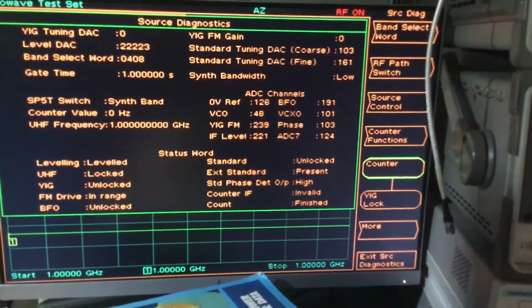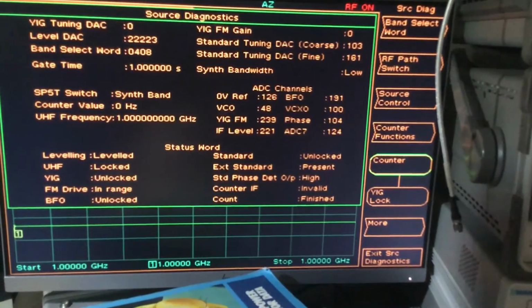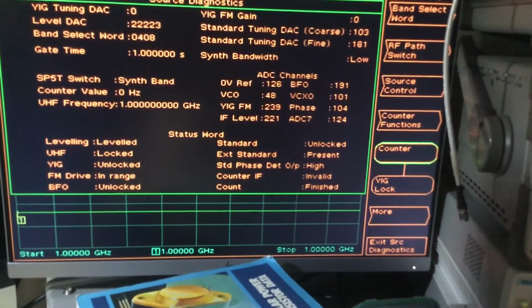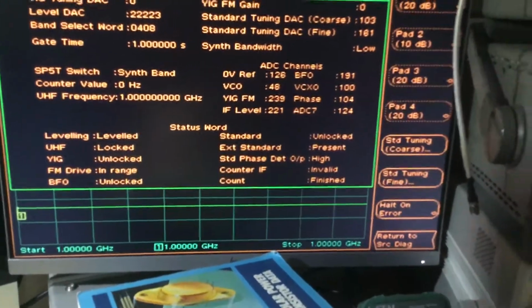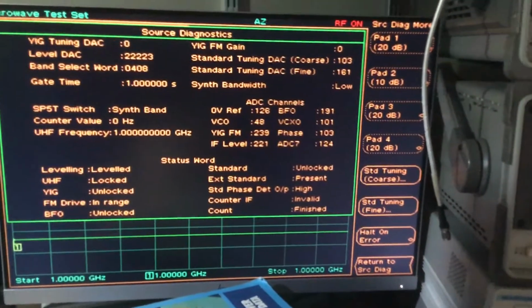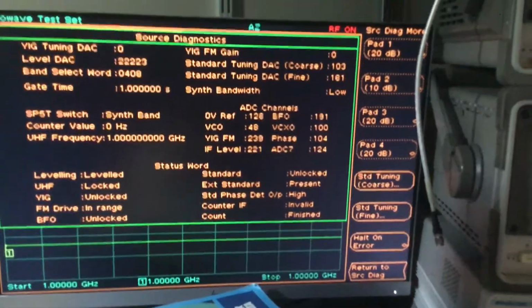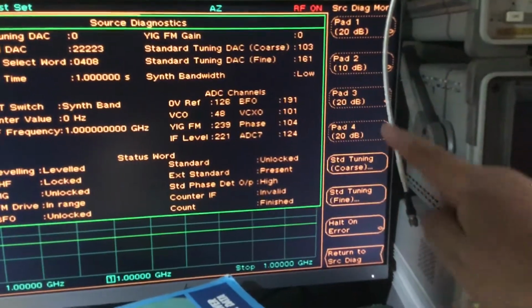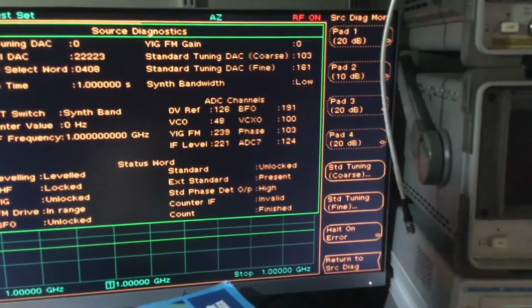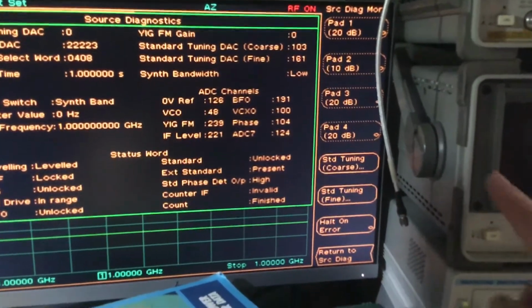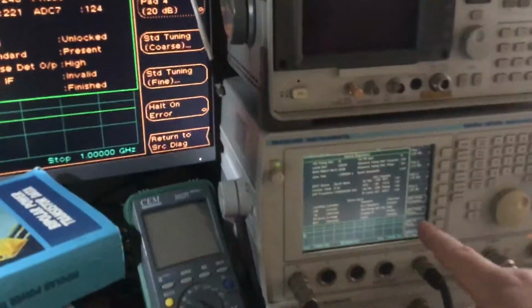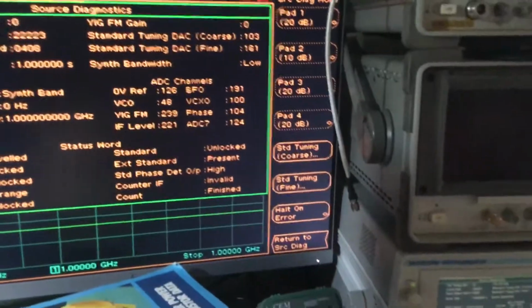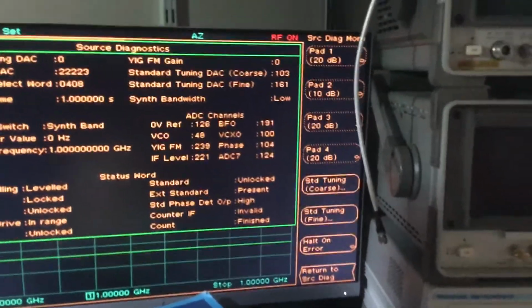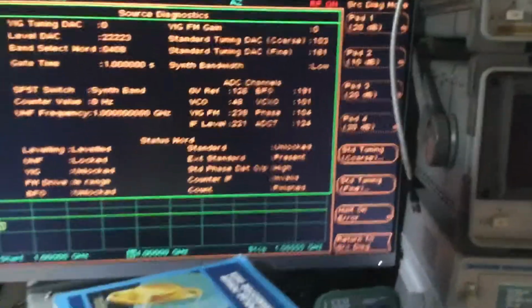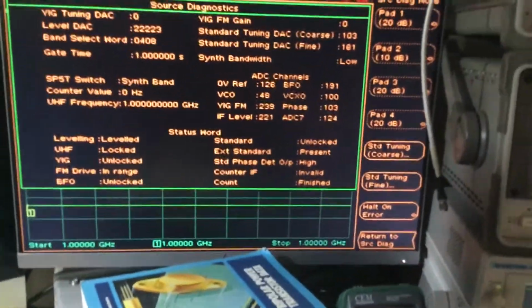We've got RF path switch, we've got source control, which we've just been in, the YIG information about the YIG locks, so we can test the actual locking of the YIGs separately. And then we have the step attenuator option as well, which we can test using this menu here. These are the pads you can switch in and out when the step attenuator's on. They're greyed out on this particular test set because this one doesn't have a step attenuator in it, but the test set that I'm currently repairing does have a step attenuator in it, and they're highlighted when you're in the service menu on that test set.